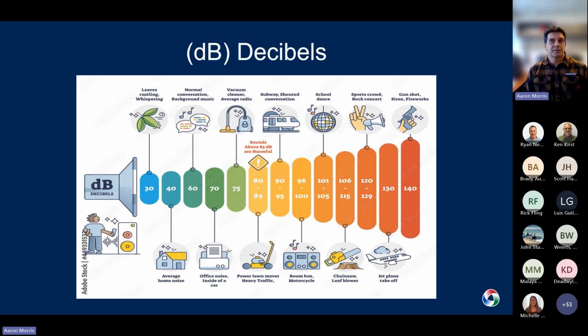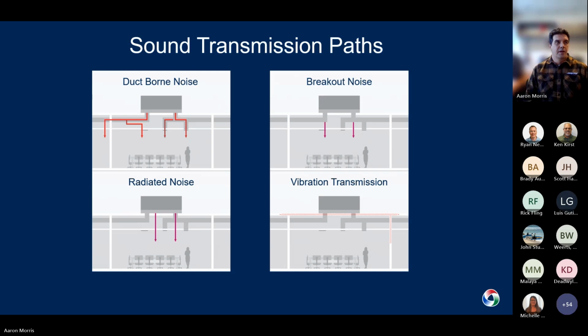The CHPS prerequisite requirement is a dBA of 45. So you would have to design for that target in order to meet the CHPS certification. If you want to pick up some enhanced points, you're going to be looking at a dBA of 40 or 35. So you can see we're really targeting way down on the lower end of that scale. So really, very, very quiet in the space.